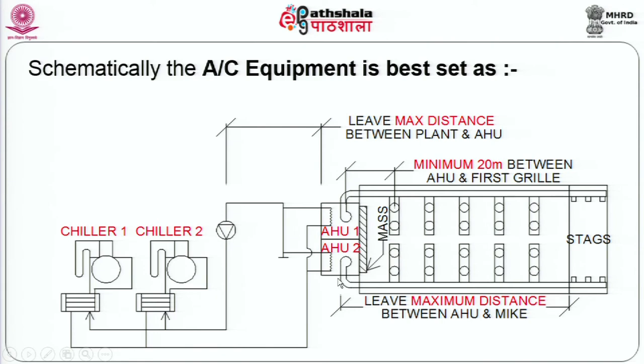Now, for salvaging that amount of space, what one does is keep this here, but attenuate this noise from going here by adding mass. This noise was attenuated by distance, whereas this noise is attenuated by mass. You make sure that this noise does not have a straight line path of travel directly to the mic which is kept here or the mic which is kept here, so that you have a fair amount of attenuation. If you notice from the placement itself, the air handling unit has been kept at a place away from the stage. That is with the view that this is the area where you have the mic which can show up the weaknesses of any noise travel into the auditorium. So, the mic is away from the noise and it is further protected by this mass. So, again you have a play between mass and distance to get you the best results.